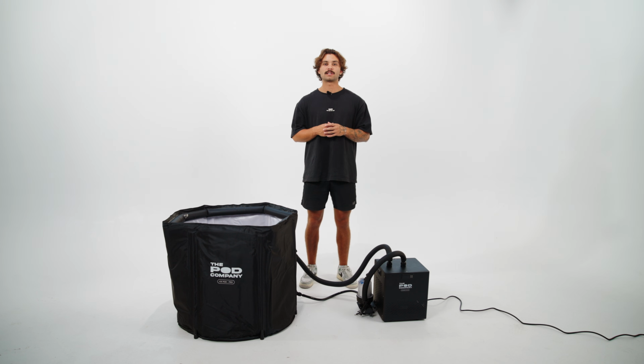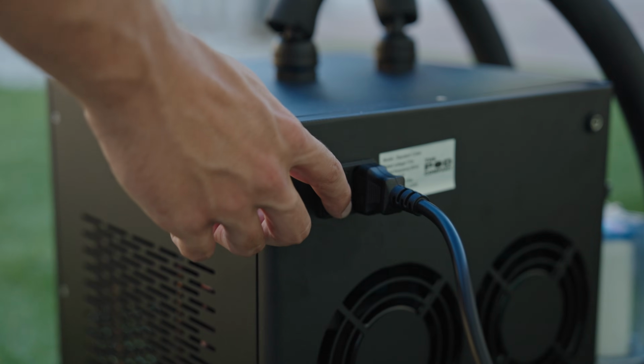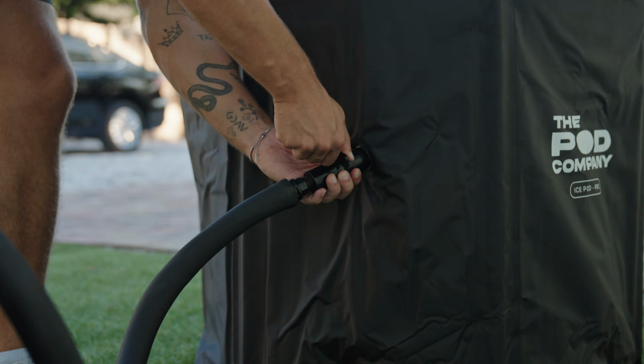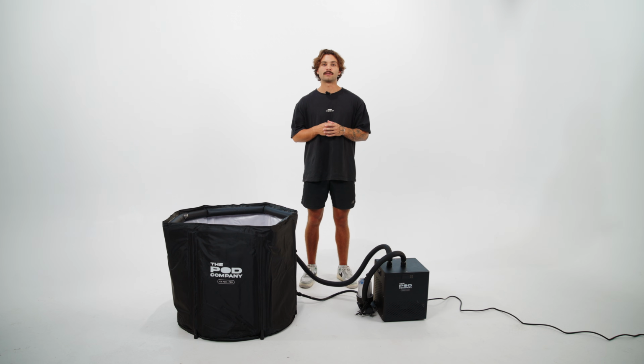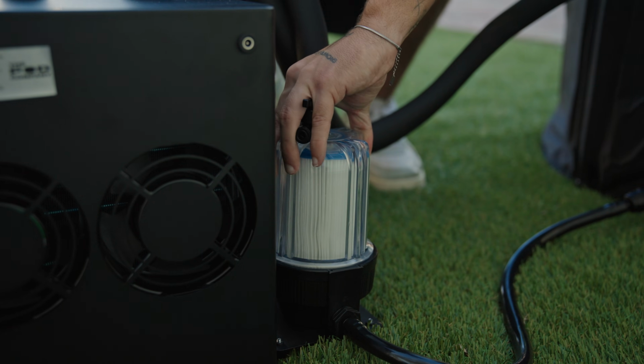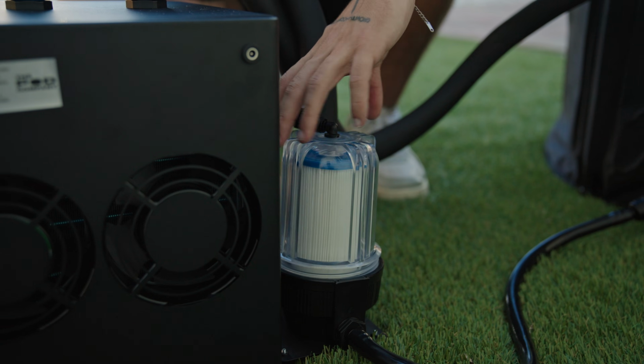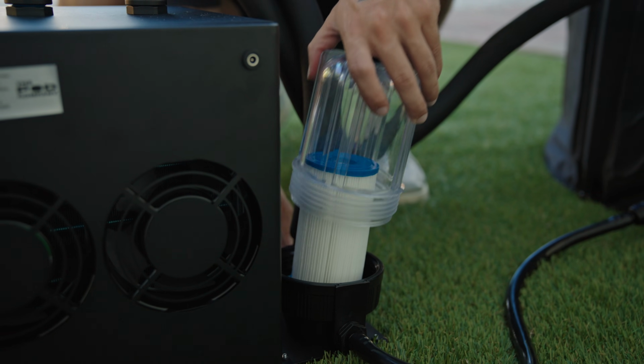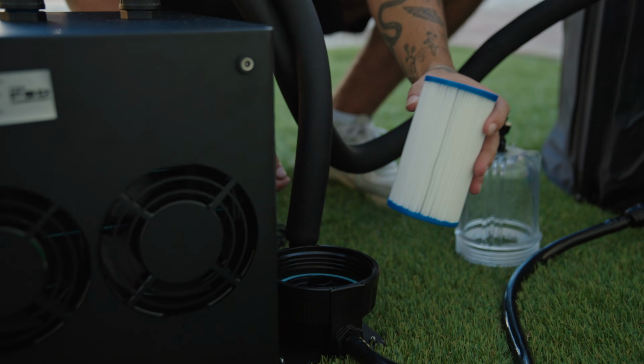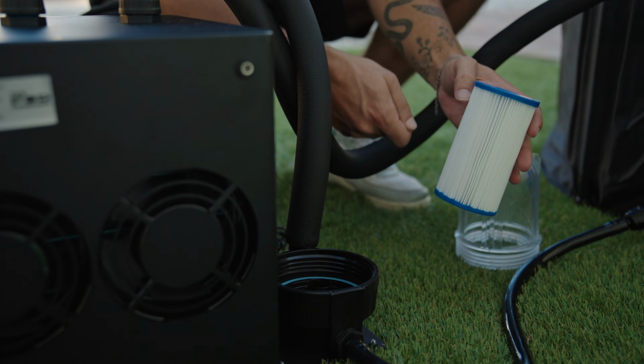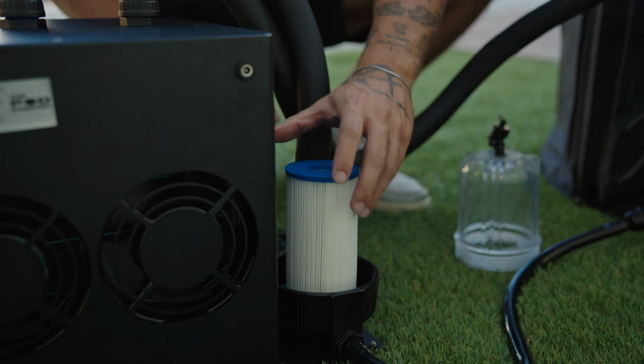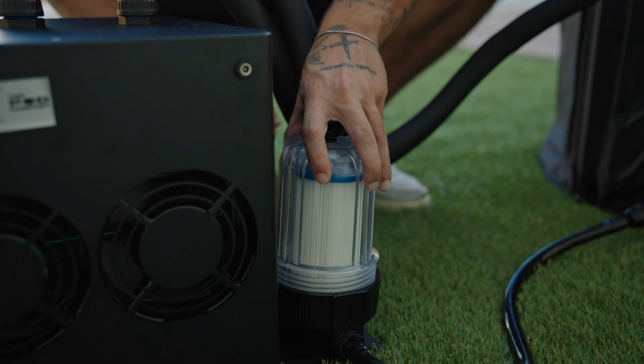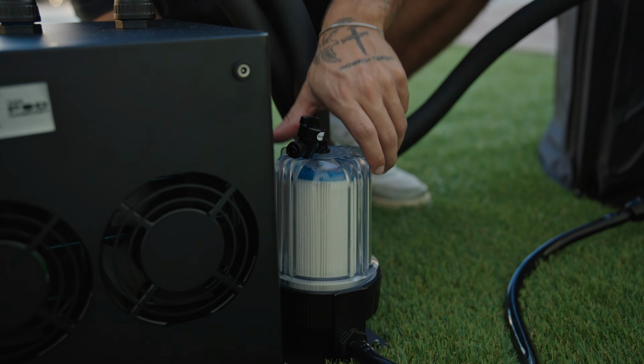To keep your chiller running smoothly, we recommend cleaning the filter every 7 to 10 days. Start by turning off the chiller, closing both valves on the IcePod, and placing a towel nearby to catch any excess water, especially if you're using it indoors. Then, remove the filter by unscrewing the filter canister counterclockwise. Once removed, rinse the filter with water using a brush or hose to clear out any dirt. After rinsing, simply reinstall the filter and tighten the housing. If it's been more than 30 days or the filter shows signs of wear, it's time to replace it.